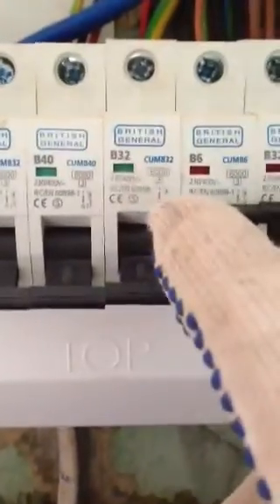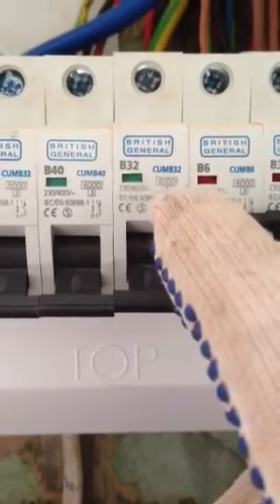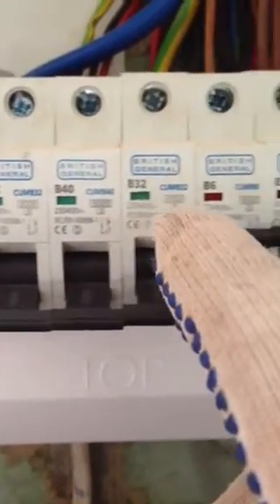So that would suggest to me we are pretty close to the local transformer here. That's done it again, exactly the same, 10 kA. People wonder that these circuit breakers have got a 6 kA value, and it's showing in a rectangle as 6,000. That's the maximum fault current they can safely disconnect. But we've got a prospective short circuit current of possibly up to 10 kA.